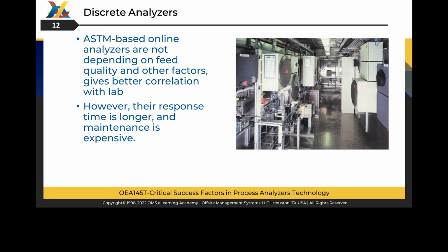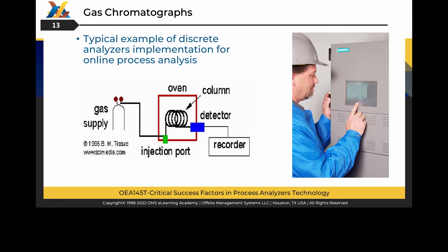ASTM-based discrete online analyzers are not depending on feedstock quality and other external factors, which gives a better correlation with the laboratory. However, their response time is usually longer and maintenance is expensive. These technologies are usually selected if no more reliable and proven technique can correlate well with the standard laboratory ASTM method. Process gas chromatography, or PGC, is a common type of discrete analyzer used in analytical chemistry to separate and analyze compounds that can be vaporized without decomposition.